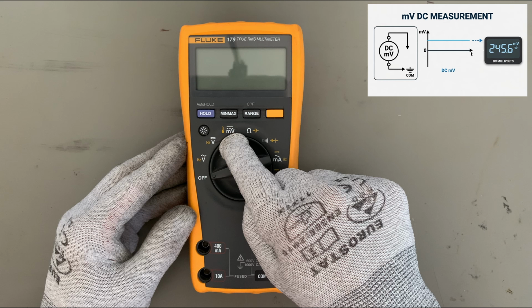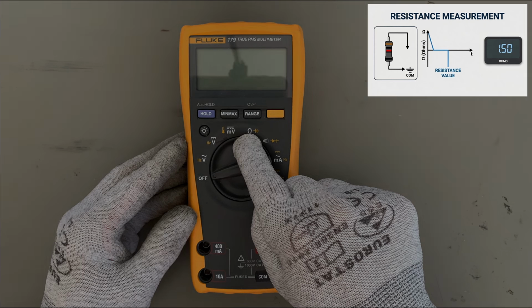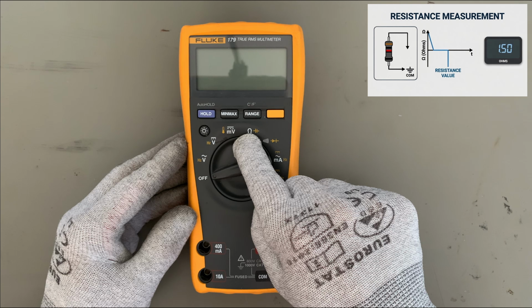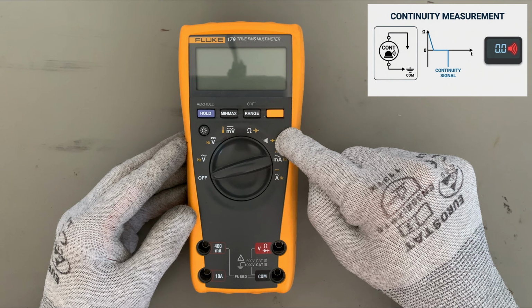Millivolts, DC, for very small voltages, sensor outputs, shunt measurements, low-level signals. On the 179 specifically, the second function here is temperature, using an external Type K thermocouple. Ohms, resistance, and behind the yellow button, capacitance. Yes, your meter measures capacitors. Most people never find out. Continuity, the beep function, fast cable and trace checking. Second function, diode test, which measures forward voltage drop across a junction.